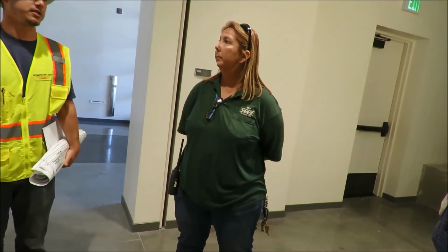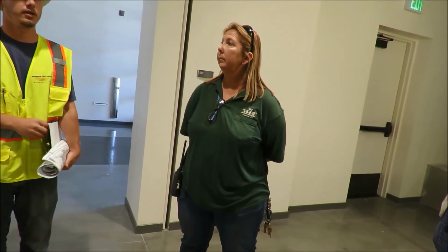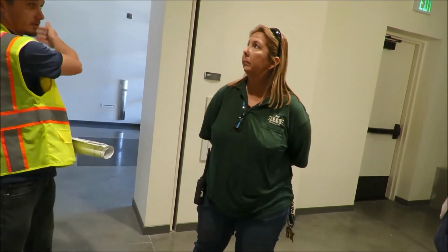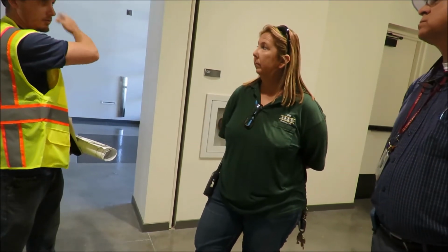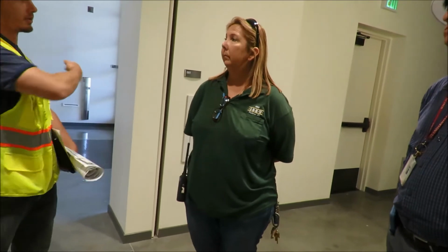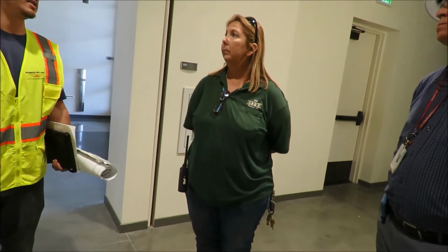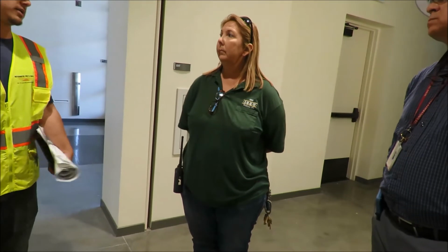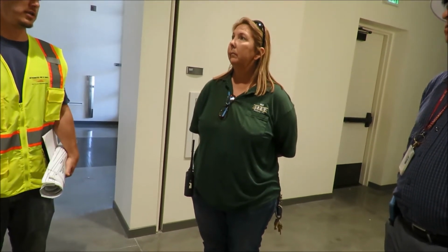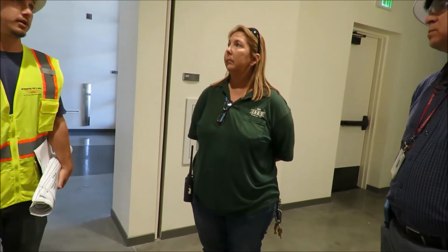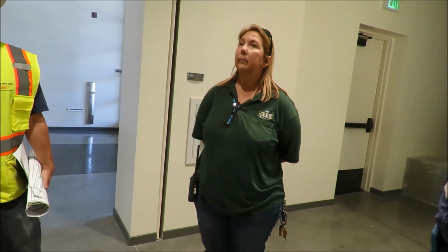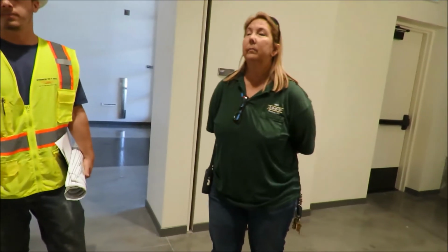As far as specialty functions, the only ones you have out here, other than closing doors, dropping the elevator to a floor other than where the alarm is, and the smoke screens, would be an HVAC shutdown. That's on general alarm as well. Everything will shut down, all airflow, and I believe almost all the exhaust fans shut off except one fan that drops down to 50%.